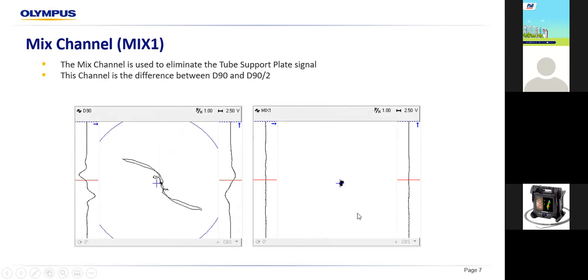So we can just focus on the mix channel only. If there's a defect under the support, you can see under the mix channel here that there is an indication. You can see here, on this presentation, there's a D90, differential 90, and then the mix channel. At differential 90, you see there's a signal, but when you go to the mix channel, there's no signal at all. That means this is a support.